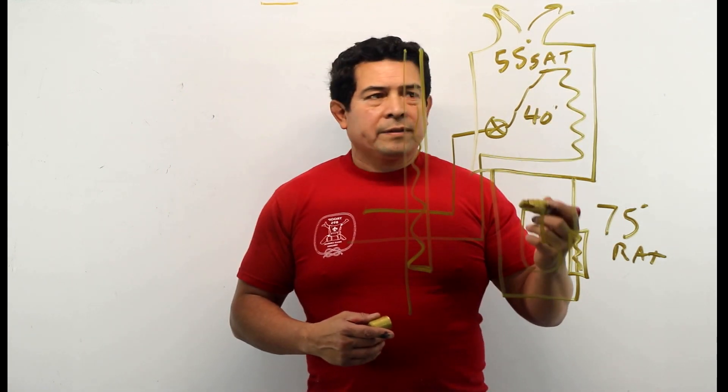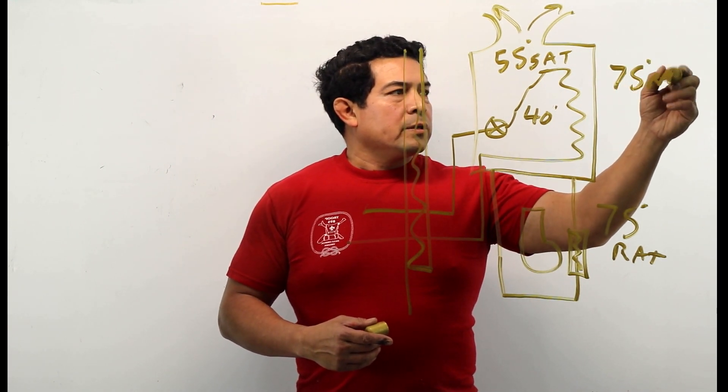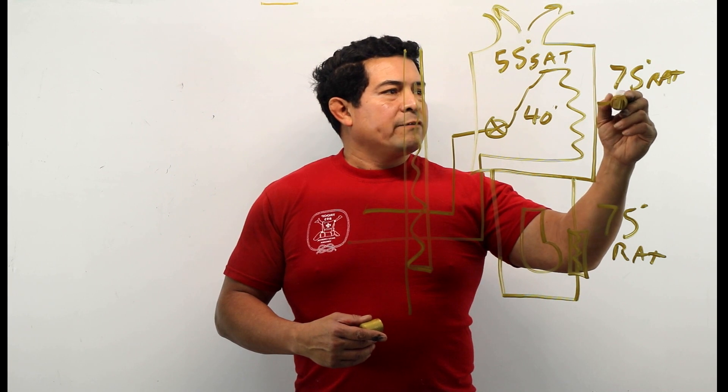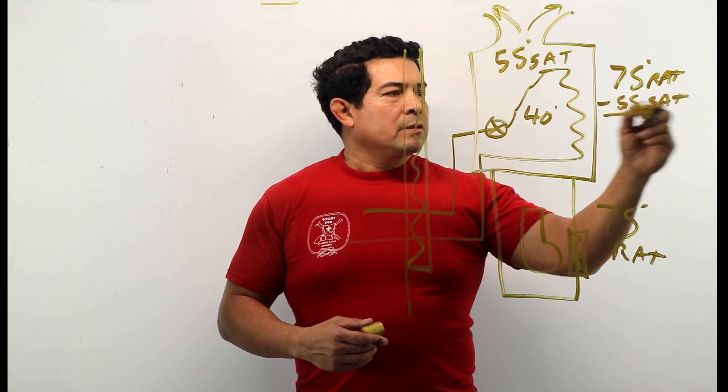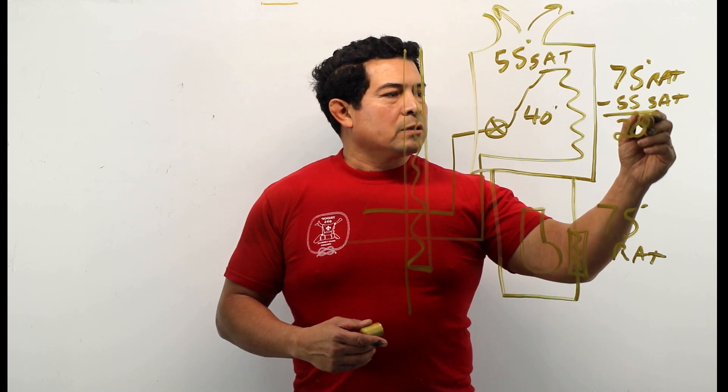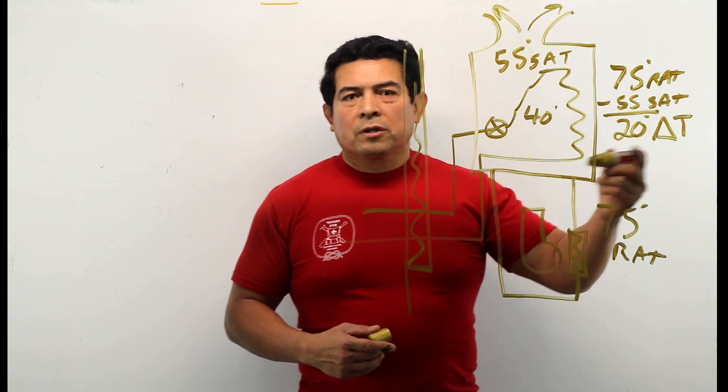So then what we have here is we have your 75 degrees return air temperature minus the 55 supply air temperature. That gives us a 20 degree delta T.